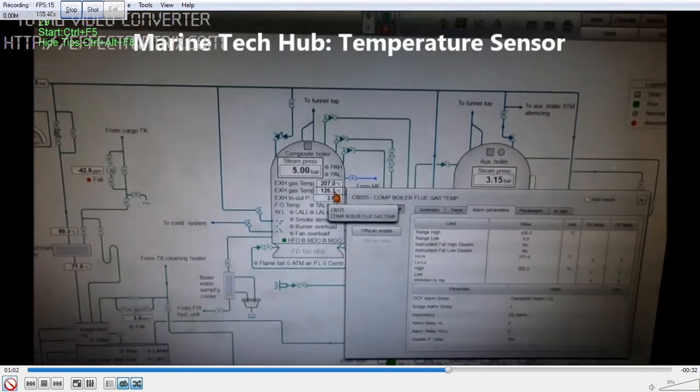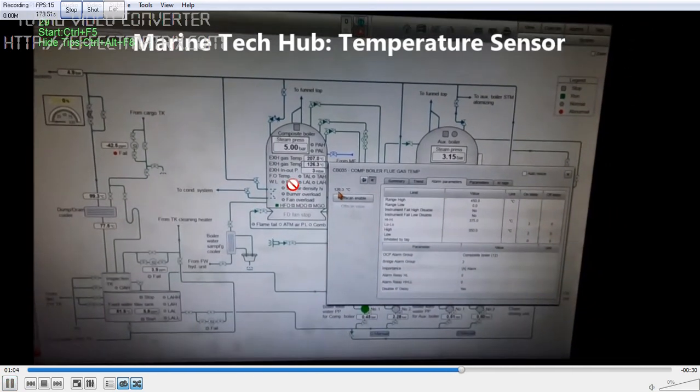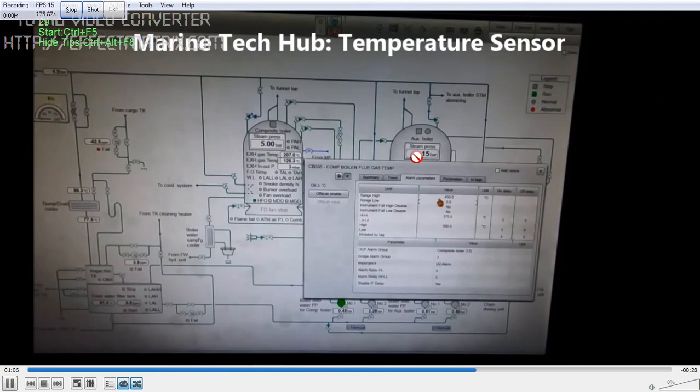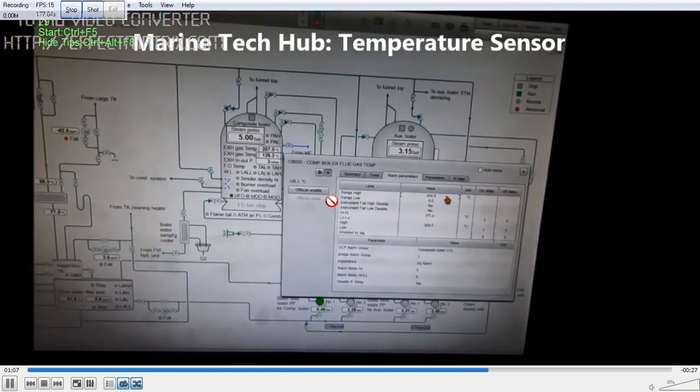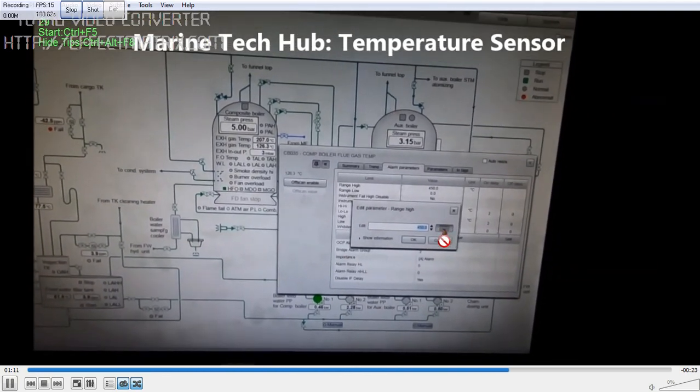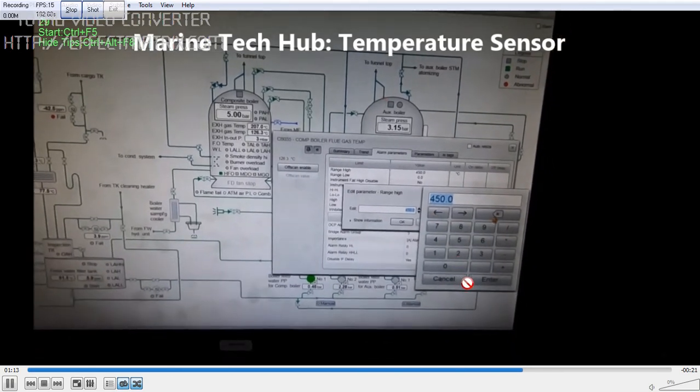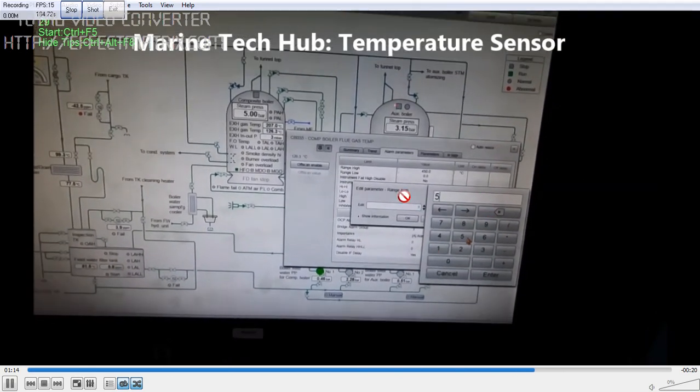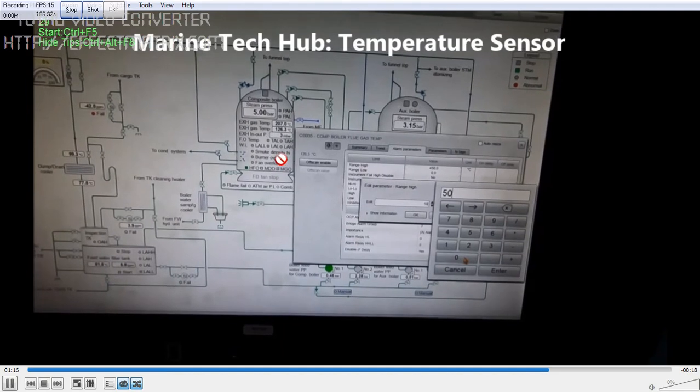So this is very important. So 126.3 here. Again when I change back to 500, you will get back the correct reading. So for electrical officer on board the ship, this is very important. If you change the correct range and change the alarm setting. Once I change back to 500, you will get the right reading again.